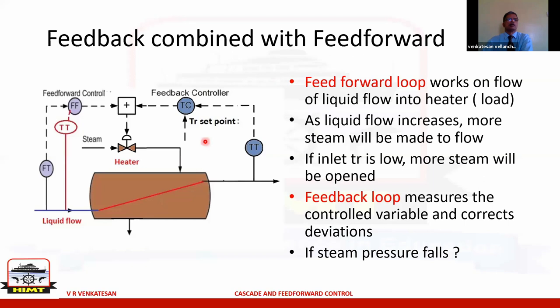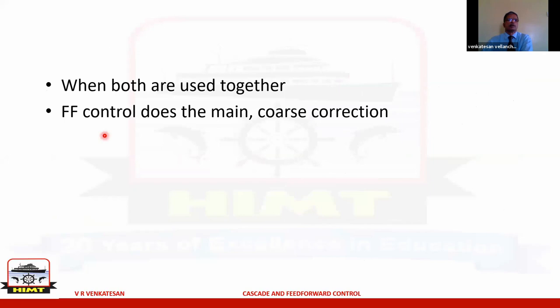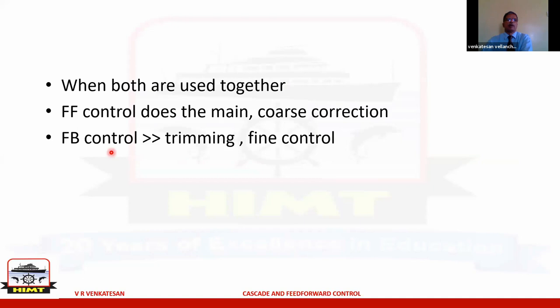Combining feed forward and feedback: the feed forward part does the main controlling, but its control is coarse — not exact. As soon as steam demand increases, feed water or firing rate increases immediately. The feedback control gives the exact final value — for example, maintaining exactly 16 bar is achieved by the feedback control. When used together, the first reaction always comes from the feed forward part, which does the bulk of the correction, while the fine adjustment is done by feedback.